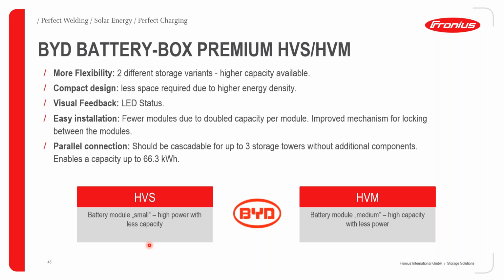So in terms of LED status, you can get to know what the battery is doing right on site by looking at the LED status that is provided with the battery stack. And for ease of installation, as I mentioned before, you can start with a few battery modules, and then you keep increasing your sizes to the required battery stack, maybe a maximum of 8 for the HVM and a maximum of 5 for the HVS series. When you stack 3 of the 22.1 HVM stacks, then you can get a maximum of 66.3 kilowatt hours.